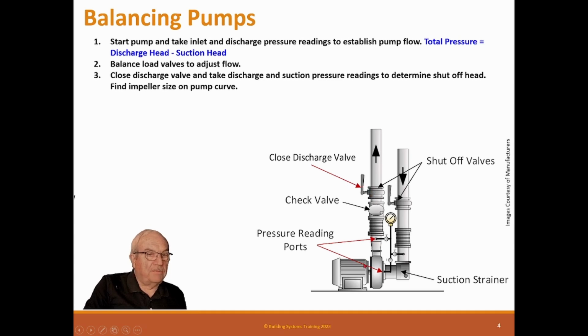But you close it, and the pump can run that way for a few seconds or a few minutes, not a very long time, because now you have this pump deadheaded. So all that horsepower in that pump is going into the water. What I'm trying to tell you is it will turn to steam very quickly. So you can't run it with the valve closed for any extended period of time. Just a few minutes, enough time for you to take these pressures, the suction pressure and the discharge pressure, then open the pump back up.